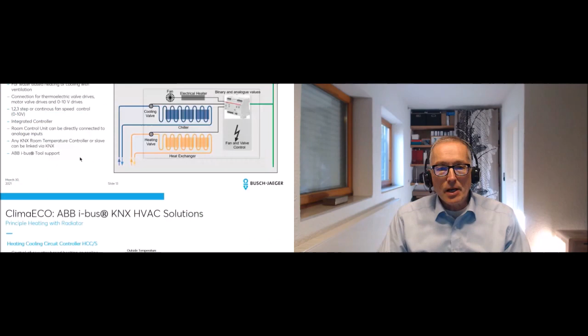Yeah, let's come to the heating cooling circuit control. So now we go out of the room a bit. We come to the more powerful solutions behind and the heating cooling circuit control. You can see here on the right, we have a mixing valve. So we mix the return flow with a flow coming from the boiler or chiller. And then we deliver the right temperature. We have an own pump in the circuit and we measure flow and return flow to control everything. Yeah, and our heating cooling circuit controller has a task to control via the mixing valve the right temperature, to turn on and off the pump, and to do this, we have to measure the flow temperature at least. Yeah, and it's a controller inside.